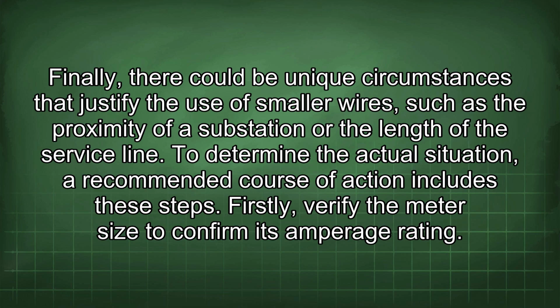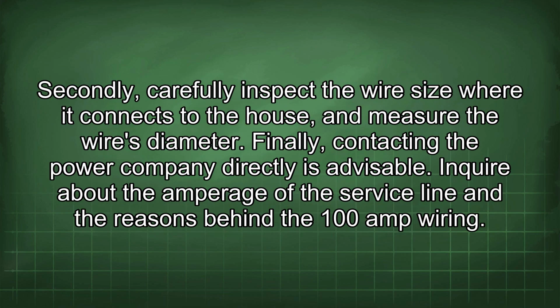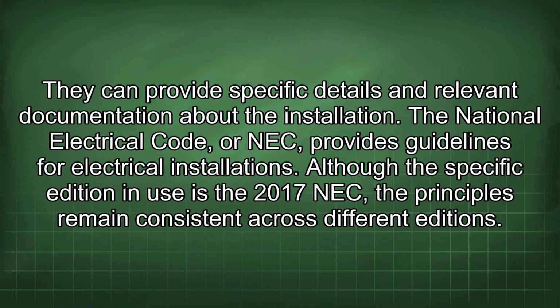To determine the actual situation, a recommended course of action includes these steps. Firstly, verify the meter size to confirm its amperage rating. Secondly, carefully inspect the wire size where it connects to the house and measure the wire's diameter. Finally, contacting the power company directly is advisable. Inquire about the amperage of the service line and the reasons behind the 100 amp wiring. They can provide specific details and relevant documentation about the installation.